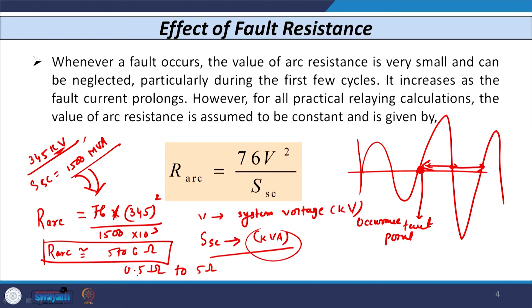So, 345 square divided by the short circuit SSC, that is the short circuit power at the fault point. That is given in MVA, so we need to convert it into kVA. So, it is 1500 into 10 raised to 3. If you solve this, it comes out to be roughly around 5 to 6 ohm. So, arc resistance normally varies from 0.5 ohm to maybe 5 or 6 ohm. So, this is fixed. Now, let us see what is the impact of fault resistance on different characteristics of distance relay.